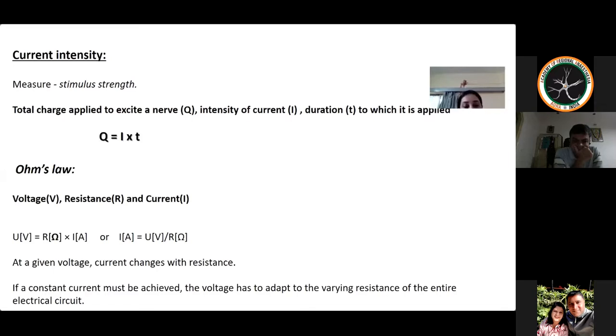So for nerve stimulation to be performed, we need a constant current. So that is done by adjusting the voltage to the varying degree of resistance. That is, the voltage has to adapt to the different resistance produced by the entire circuit. So here the voltage might increase or decrease to produce a constant current despite the changing resistance. And this resistance will be produced by the needle tip, electrode to skin interface, and the tissue layers.